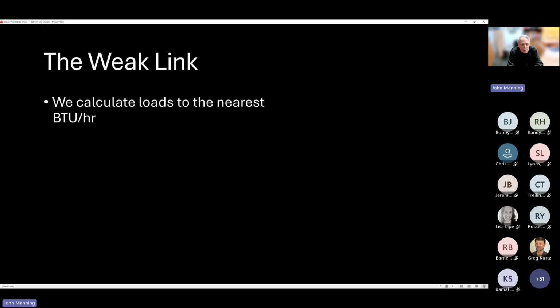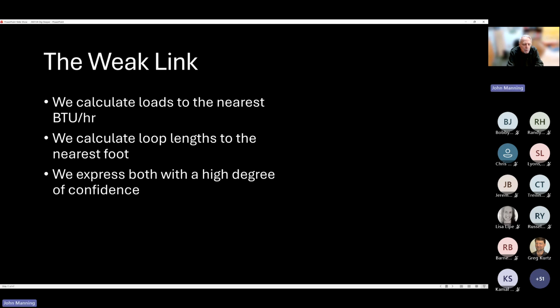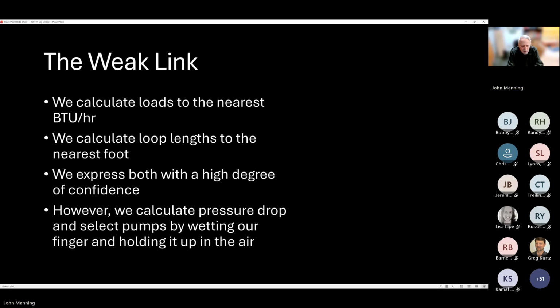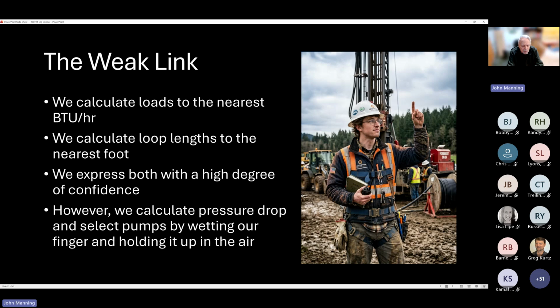Although we calculate loads to the nearest BTU per hour, and we calculate loop lengths to the nearest foot, I do get a kick out of engineering drawings that ask for a loop depth of something like 383 feet. I think we ought to round off to the nearest 50 foot, frankly. But we express both of these calculations with a high degree of confidence, and that reflects a degree of accuracy. However, when we calculate pressure drop and select pumps, we generally wet our finger and hold it up in the air, because it's a tedious process.